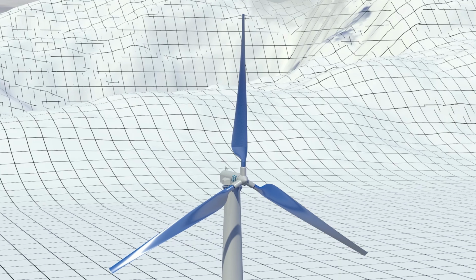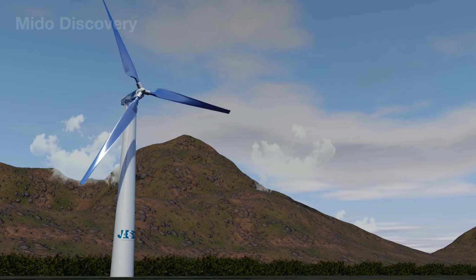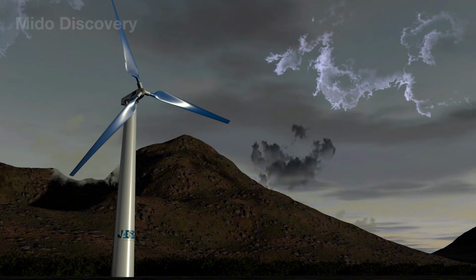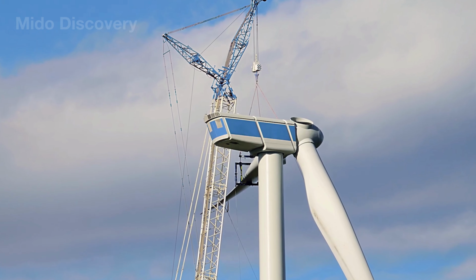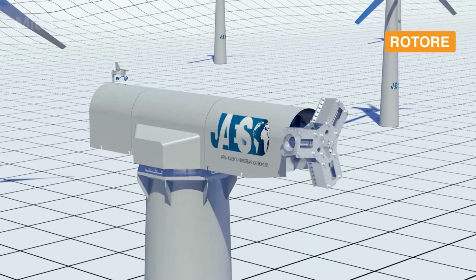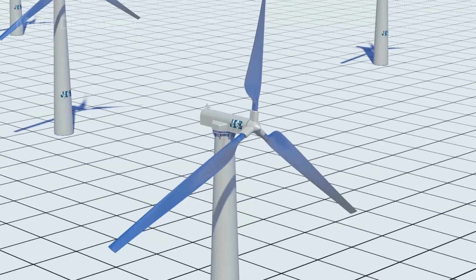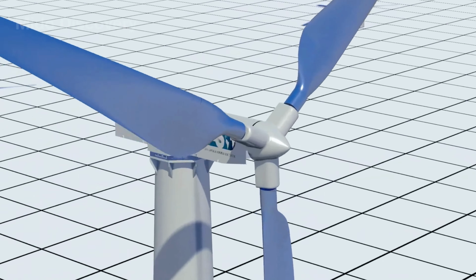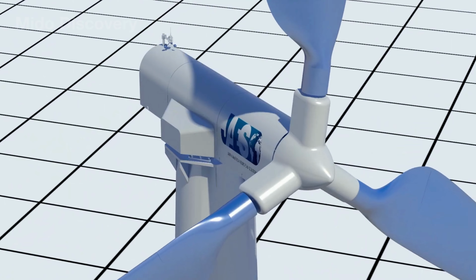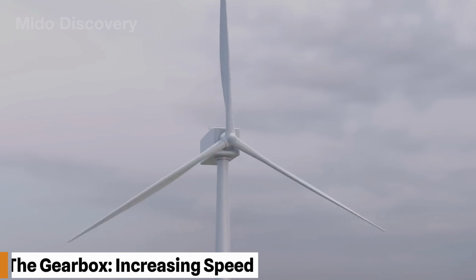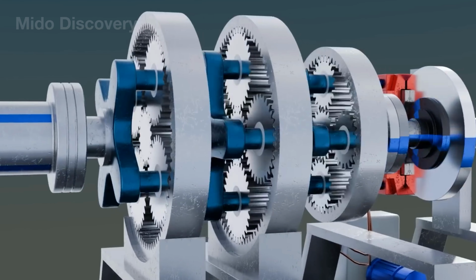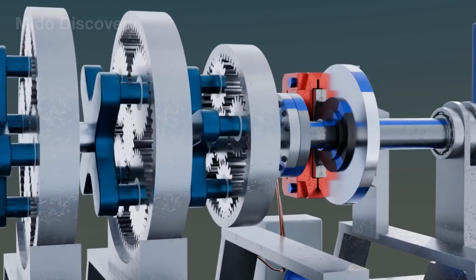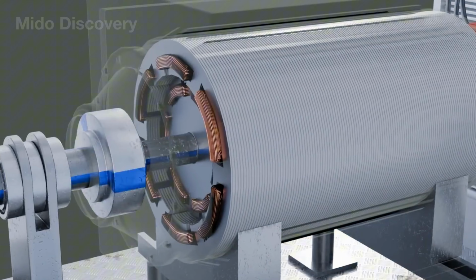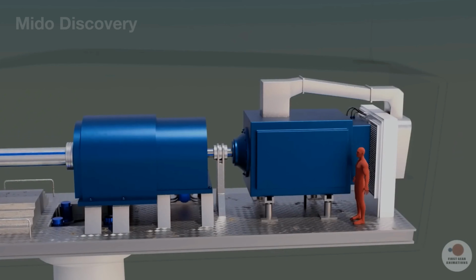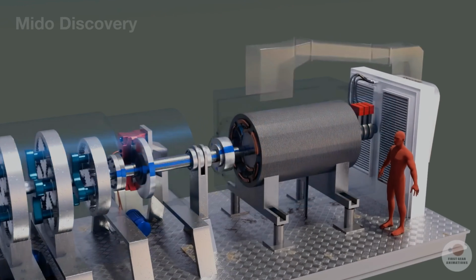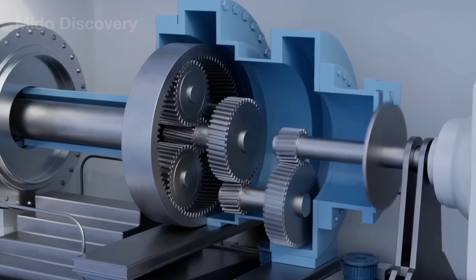Although the rotor rotates at only about 10 to 20 revolutions per minute, the main drive shaft must handle an enormous amount of torque. That's why it is made from high-strength steel and built with a large diameter, allowing it to operate reliably for decades. If the rotor were connected directly to the generator, the turbine would produce very little electricity. The reason is simple: the rotor spins too slowly. That's where the gearbox comes in.